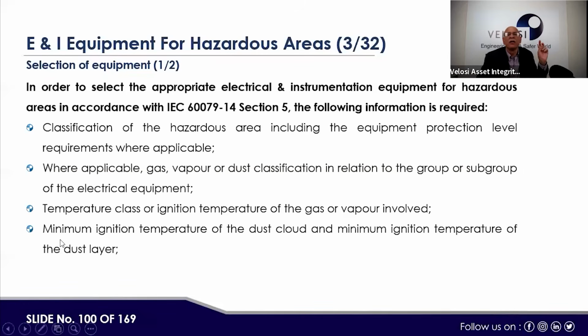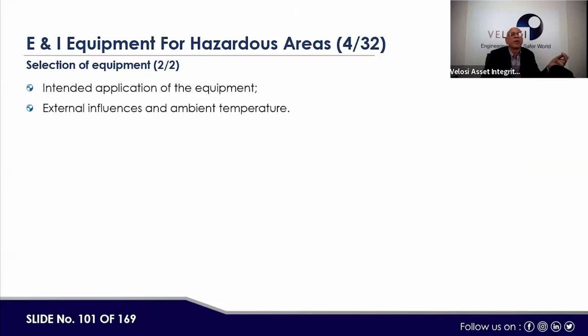Classification of the hazardous area, including the equipment protection level requirement where applicable; gas, vapor, or dust classification in relation to the subgroup of the electrical equipment; temperature class or ignition temperature of the gas or vapor involved; minimum ignition temperature of the dust cloud, and minimum ignition temperature of the dust layer. Dust we did not cover, but keep in mind the properties are required for both the gas as well as the dust. Then the intended application of the equipment, external influence, and ambient temperature of that particular equipment.